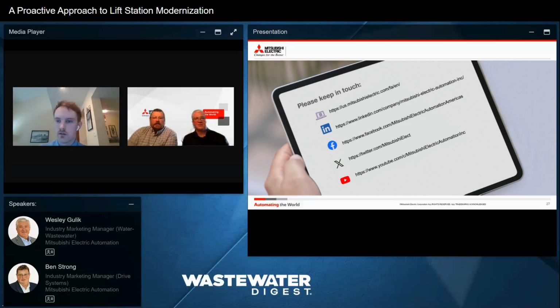All right. Next question we have here is, what percentage do you see of VFDs that have electrical bypasses, whether that be across the line, soft start, or VFD? And they said, we mainly have small horsepower pumps here in rural Texas, so a costly endeavor to get this built-in feature. And I could try to answer this question. It's definitely changed over the last 20 years. Variable frequency drive technology is becoming much, much more reliable. I think that's one of the reasons why bypass systems were put into place. With the electrical bypass, it also depends on the application, the process, that, hey, I cannot afford the system to be down. So this is the reason why I will put in a bypass.